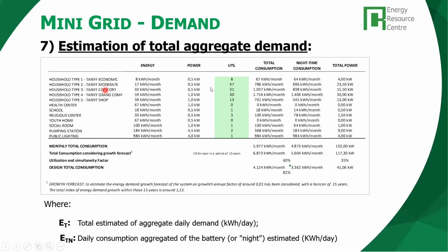You see, for instance, for the houses, we have 8 families for type 1, 47 families type 2, 31 families type 3. Okay, altogether, this will give the total number of connections that you can have in a mini grid. This is going to be in the range of 140 connections for a community. What is the total consumption for each type of customer, and the nighttime consumption? So the second very important result of the demand analysis is what is the battery or the night demand. In this example, we have roughly 82% of the demand that is going to be nocturnal. And we also look at the power consumption. What will be the power consumption for each of the segments of the customer type?